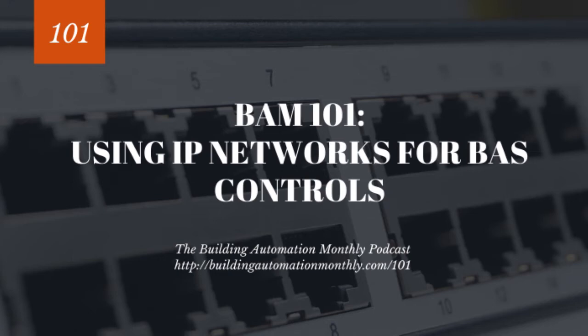IP, internet protocol, is simple: you put an IP address on every device. The advantage is no matter what medium the IP address sits on, it's all connected by the same tools. Eventually wireless has to go back to a switch, a cell modem has to go back to a switch, physical Ethernet or fiber all goes back to a switch, but they're all on the same protocol, so they all speak the same language. That means you could take any IT-based tool, like Wireshark, ExtraHop, or SolarWinds, connect all these devices together, monitor them, and troubleshoot them using standard IT-based tools that exist in the world today.